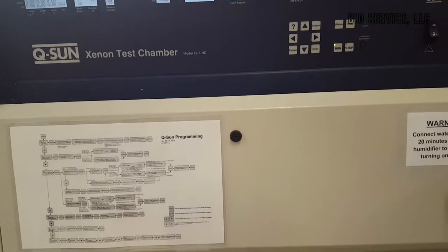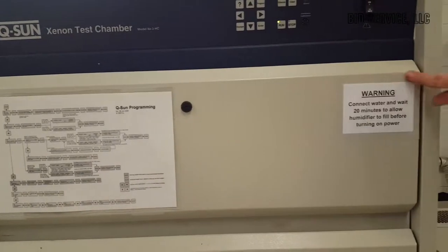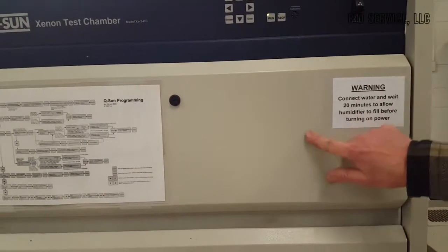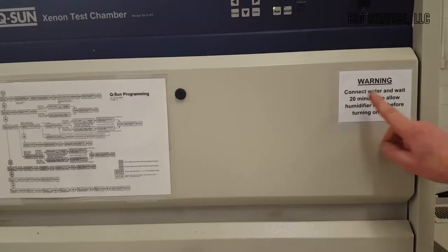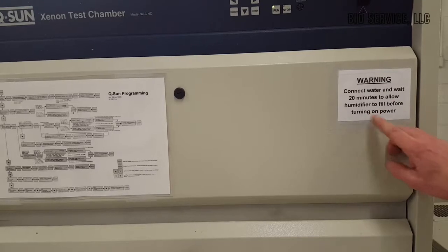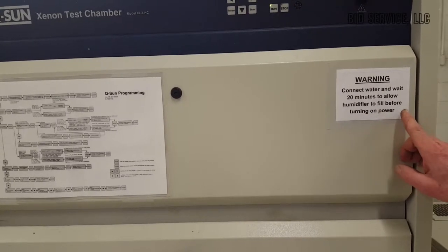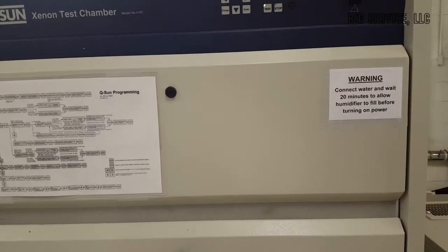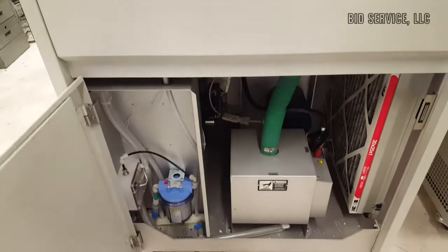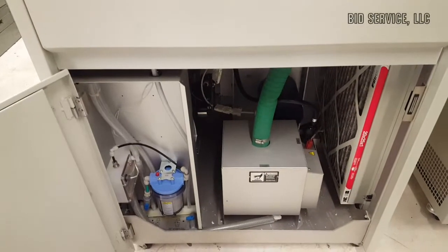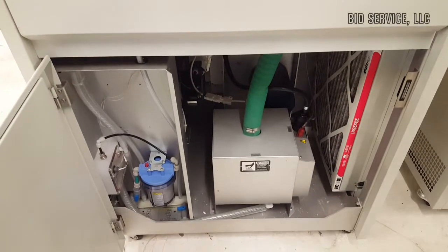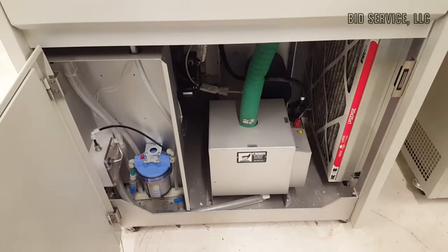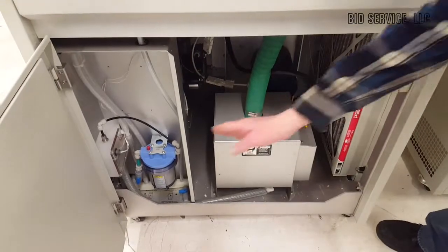One thing that I posted while we were waiting to come back here is I made this little sign. It's important. Connect water and wait 20 minutes to allow a humidifier to fill before turning on power. That is to make sure that when you first bring the system on, you don't start heating anything up until the water is completely full.